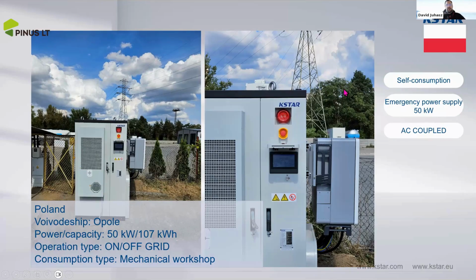Currently, the system is operating smoothly, and the investor is not concerned about temporary disconnections. The previous system had an emergency output of 50 kilowatt. However, this is not the maximum we can offer, because the new generation KSTAR inverter can be connected in parallel up to 6 units, and this is only one. And the system is AC coupled without photovoltaic panels.